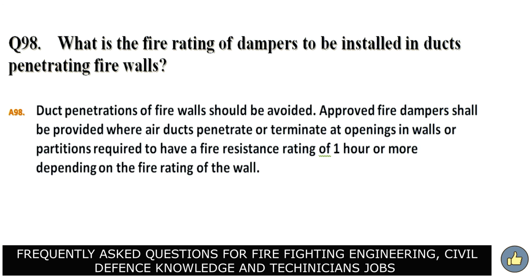What is the fire rating of dampers to be installed in ducts penetrating firewalls? Answer. Duct penetrations of firewalls should be avoided. Approved fire dampers shall be provided where air ducts penetrate or terminate at openings in walls or partitions required to have fire resistance rating of 1 hour or more, depending on the fire rating of the wall.